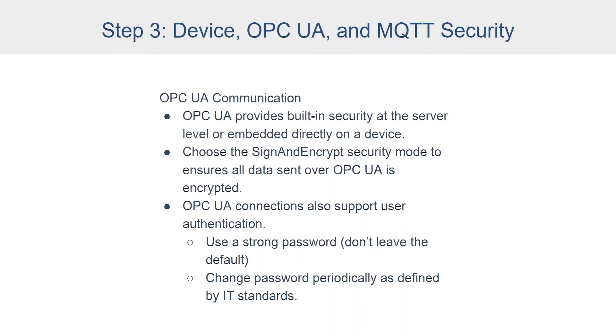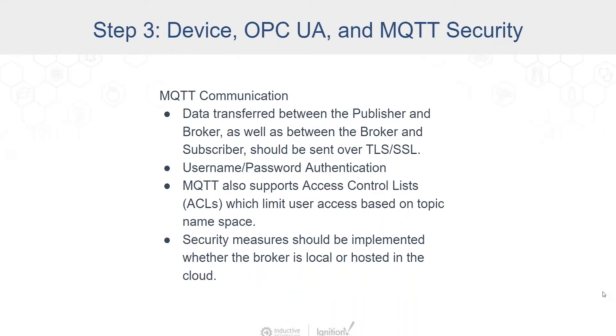When you install Ignition, there are default passwords and you should change those, even though we do default to requiring a certificate to be approved for new connections — so it's not like somebody can just connect to your OPC server willy-nilly using that password — but you should still absolutely change that. Another way to transmit data, other than OPC, is with MQTT. MQTT is a PubSub protocol. If you haven't heard of it, you should definitely go and learn more about MQTT.